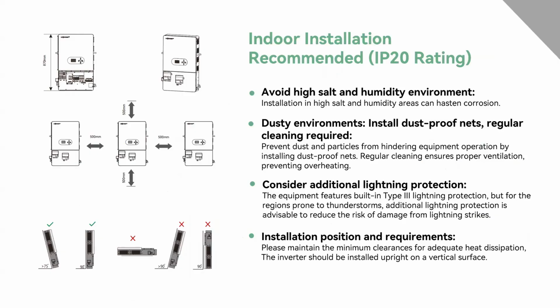Okay, so we have learned some basics of the SNA 12K. Now we need to choose a suitable installation site. Since the IP rating of the SNA 12K is IP20, we have to avoid high salt and humidity environments, as installation in such areas can hasten corrosion. If we install the inverter in a dusty environment, we have to install a dust-proof net, and regular cleaning is also required for heat dissipation and the regular operation of the inverter.